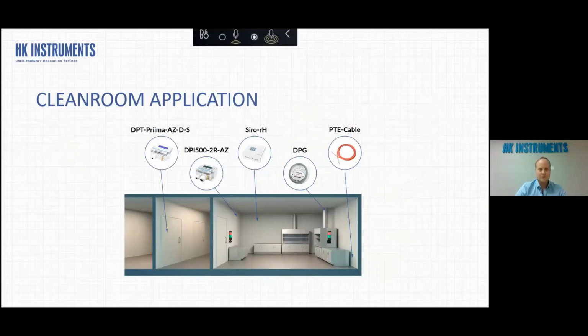And the last, we have the clean room application. We have been working in this sector for many years because our device is well suited for it. So basically, the typical measurements that we do for clean rooms are humidity, temperature, and small differential pressure. What comes to pressure, we typically set it so that we need to know the pressure differences between the corridor and the clean rooms and maintain those, let's say ±10.